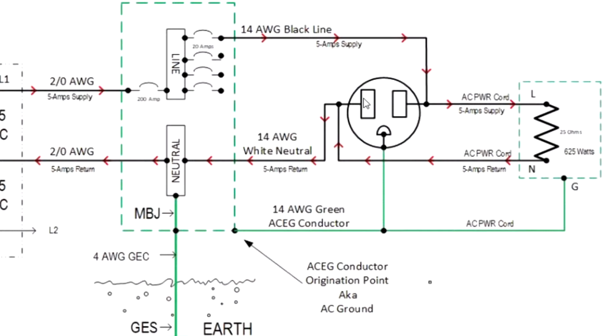If we're drawing a lot of power, say this was a toaster oven drawing 1,500 watts, we may see as much as 2 to 3 volts. And if we see 2 to 3 volts here, we know we've got just about that much sag on the line. So our total line loss would be 4 to 6 volts. Everyone see and understand that? Because we're taking loss on this conductor and we're taking loss on the neutral, there's going to be a voltage loss along the lengths. So we're looking at a voltage sag, and that's one measure of power quality.